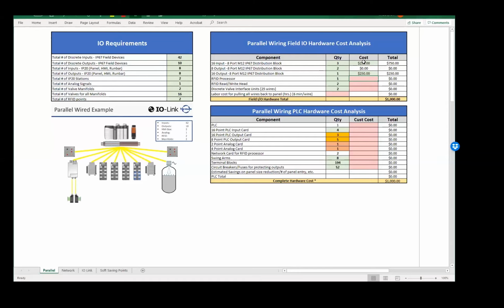RFID processor, we need that processor to be serial to communicate directly back to the PLC. MSRP on that is $2,500. Well, okay. That processor can only support two heads, which in this case is lucky for us because we only have two RFID points. Yep. And each one of those antennas is about $1,500. Wow, that adds up quick. And then each of those valve stacks has like a 25-pin D-shell commonly.